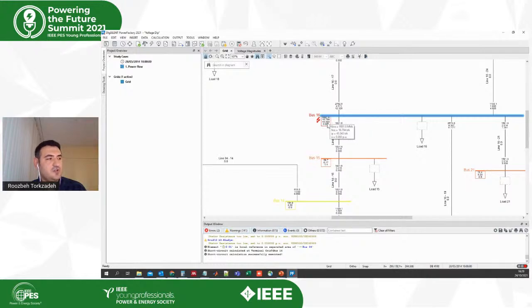For example, in this result box, you can see that the short circuit power is 9.981 gigavolt ampere, and the short circuit current is about 16 kiloamps. But also you can see the voltage at this bus bar equals 0 per unit. Which is rational because we had no fault impedance and we expected to see 0 for the voltage at this bus bar.